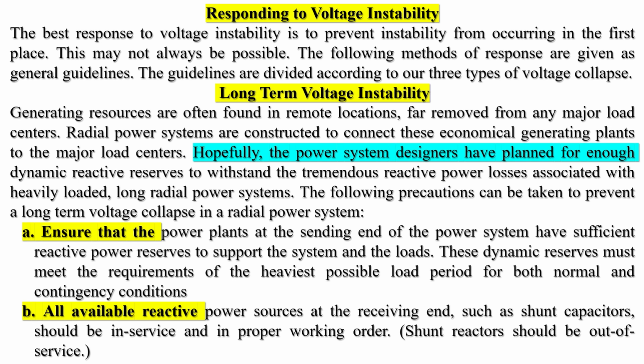Long-term voltage instability. Generating resources are often found in remote locations, far removed from any major load centers. Radial power systems are constructed to connect these economical generating plants to the major load centers. Hopefully, the power system designers have planned for enough dynamic reactive reserves to withstand the tremendous reactive power losses associated with heavily loaded, long radial power systems. The following precautions can be taken to prevent a long-term voltage collapse in a radial power system.